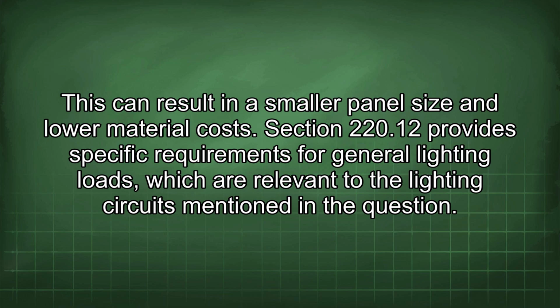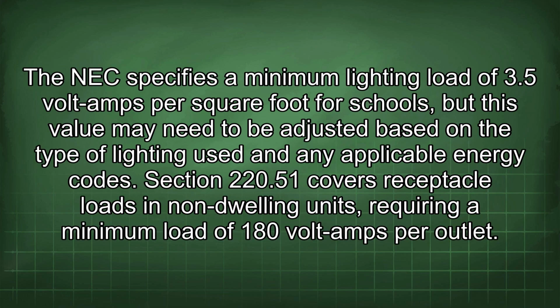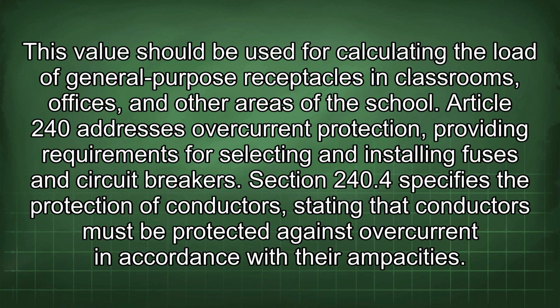Section 220.12 provides specific requirements for general lighting loads, which are relevant to the lighting circuits mentioned in the question. The NEC specifies a minimum lighting load of 3.5 volt-amps per square foot for schools, but this value may need to be adjusted based on the type of lighting used and any applicable energy codes. Section 220.51 covers receptacle loads in non-dwelling units, requiring a minimum load of 180 volt-amps per outlet. This value should be used for calculating the load of general-purpose receptacles in classrooms, offices, and other areas of the school.